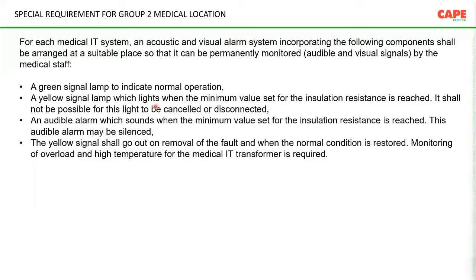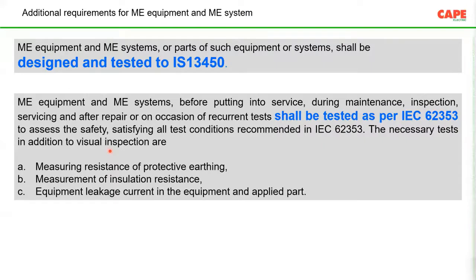Then again, for medical IT, in case of a single fault, or in case of any insulation resistance reduction, what you should do is also very well documented. Now, the other requirement. So far, the last 2 slides I was showing were about the requirements of the medical IT system. That means the OT panel, as you generally call it, is one safety measure. But the additional safety measure is the ME and the ME system.